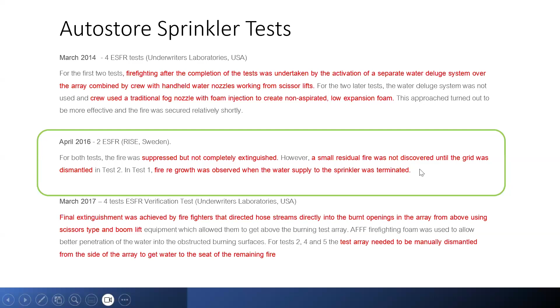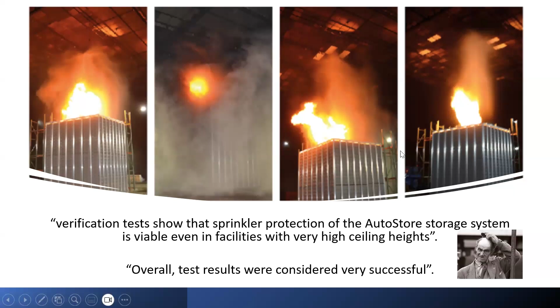And that's what these tests look like. So they were quite big tests, but still not as big as the real thing. So this is 5 meters by 5 meters by 6 meters high. And these tests were summarized by saying, verification tests show that sprinkler protection of AutoStore storage systems is viable even in facilities with very high ceiling heights. Overall, test results were considered very successful. Now, I look at the same evidence and I don't see success, but we can convince ourselves because maybe that's what we want to see. Evidence is evidence.